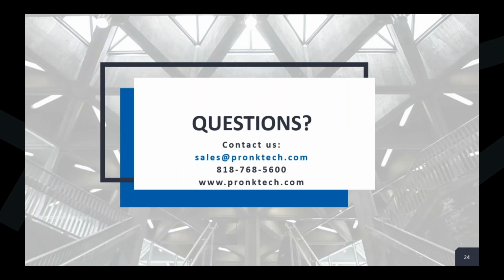Another thing we do in our service reports to try to make it easy, I don't know if you guys are familiar with the ZOLL. I always use the ZOLL as my example because in their checklist, physical inspection is 14 steps, and on their checklist you need 14 check marks. We try to make it easier on you. We have one line that says physical inspection pass/fail, and you can hit an info button and it lists those 14 steps. I like that because the first time you're doing it this year, or you've never done one, you have all the steps so you know what you need to do. But if you've been doing ZOLLs all month, you know the steps so you can just hit pass.